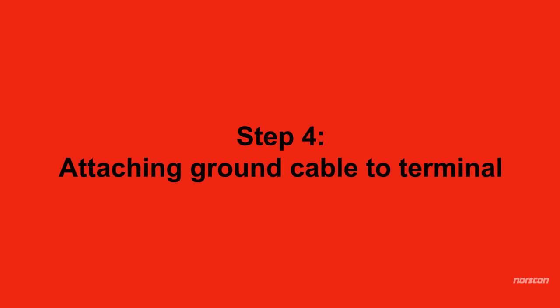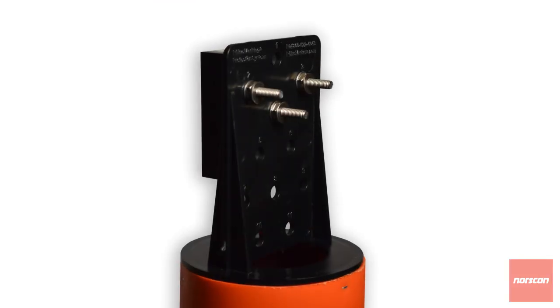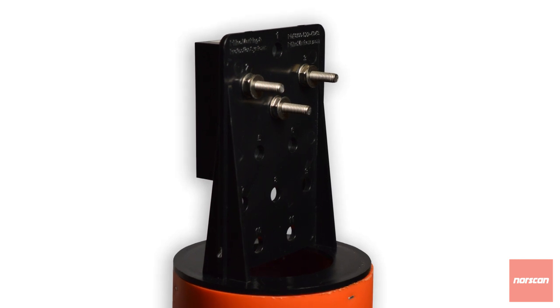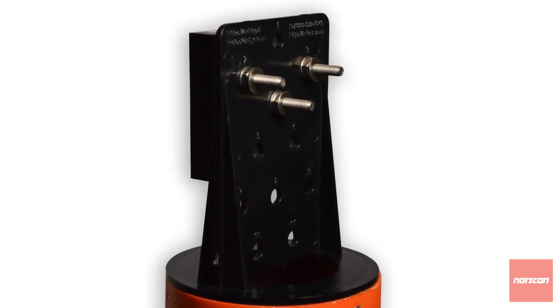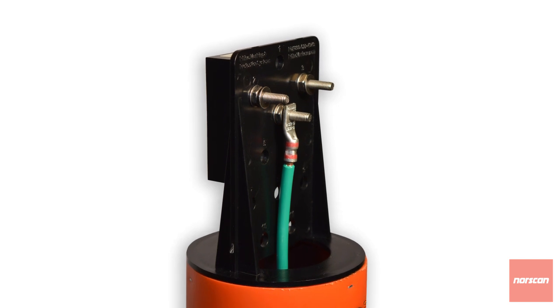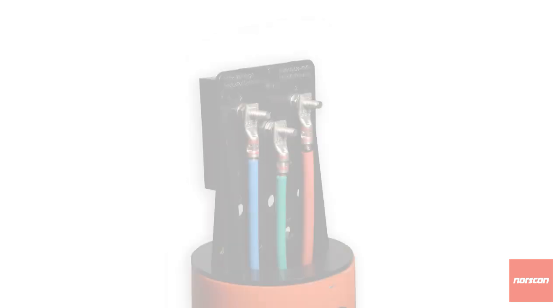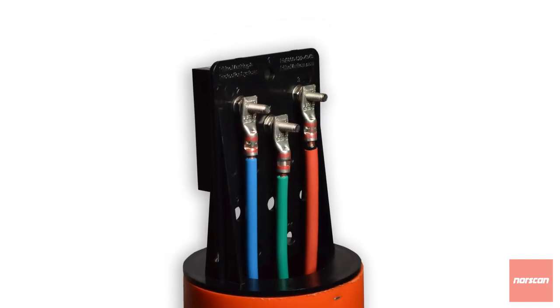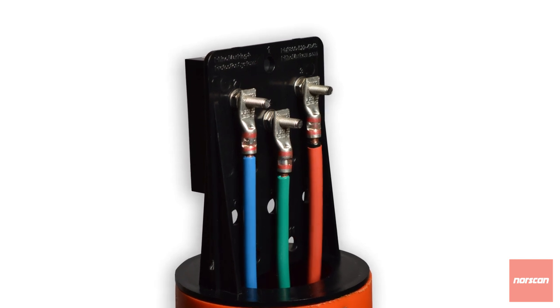Step 4: Attaching Ground Cable to Terminal. Add one washer, then one nut, and then another washer to each terminal stem post. The ground cable attaches to the number 4 center terminal post. Connect the remaining two leads as per your company color code and direction specs.